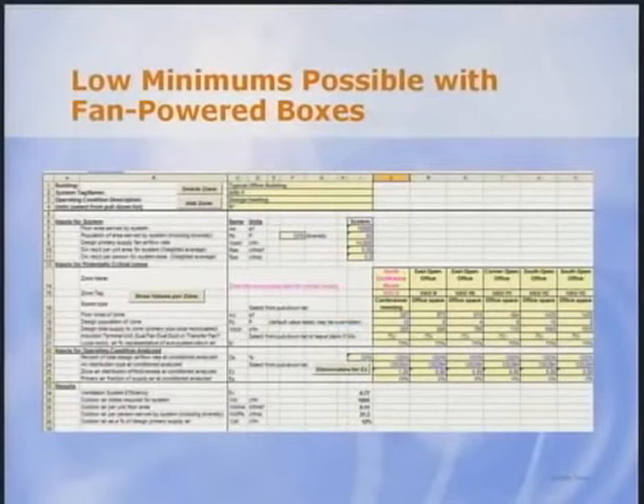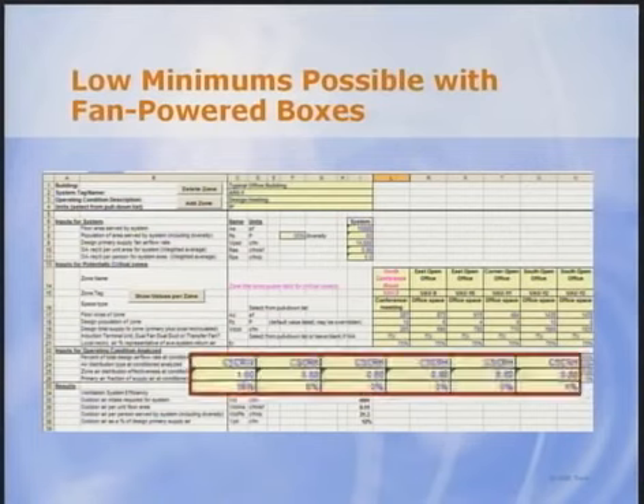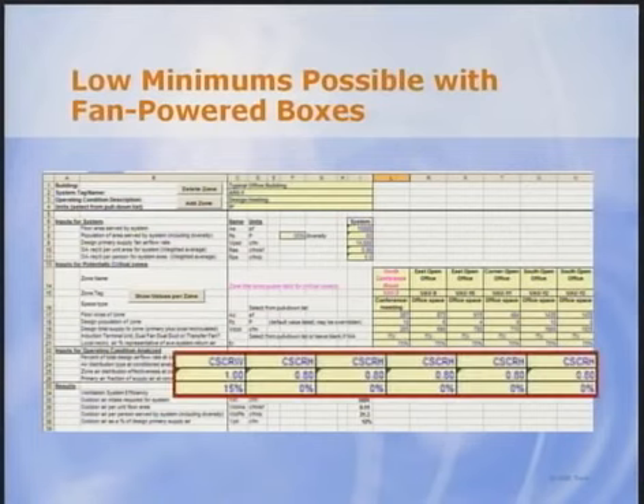In the previous slide, we saw how use of fan-powered boxes in critical zones can reduce design outdoor air rates by 50% compared to VAV reheat systems. But what happens if we use fan-powered boxes in all other zones? The answer is almost nothing with respect to outdoor air rates. The critical zones dominate in that regard. But fan-powered boxes can nevertheless be beneficial in non-critical zones. They can allow the primary air minimums to be low or even zero, virtually eliminating reheat losses and reducing primary fan energy.